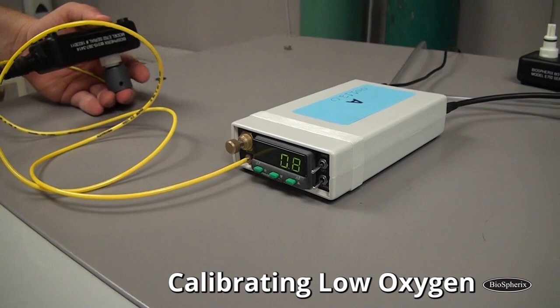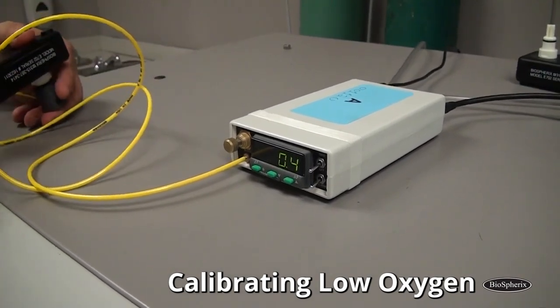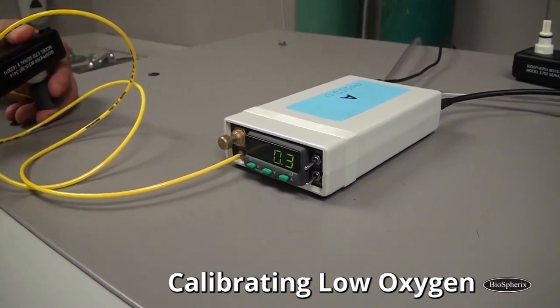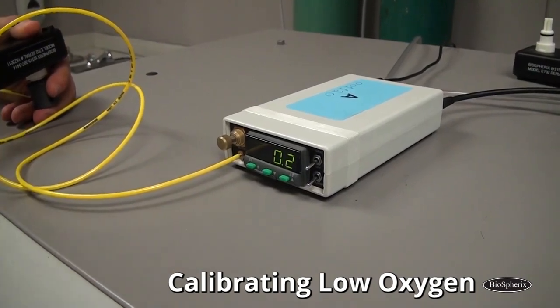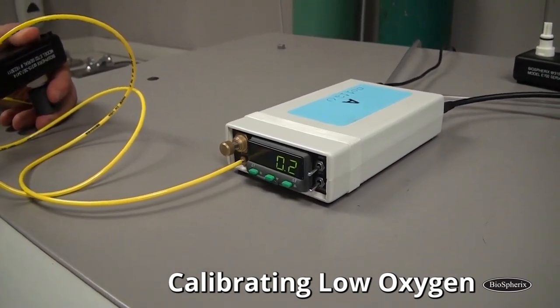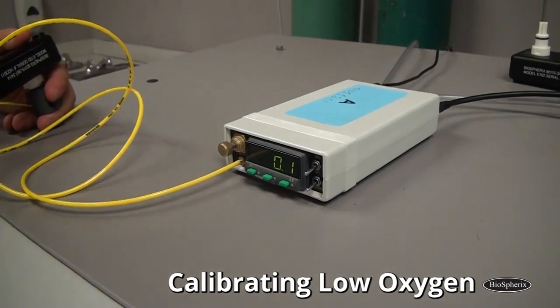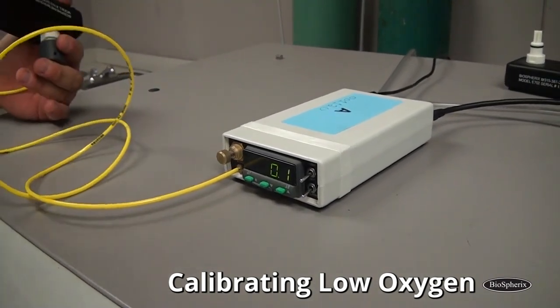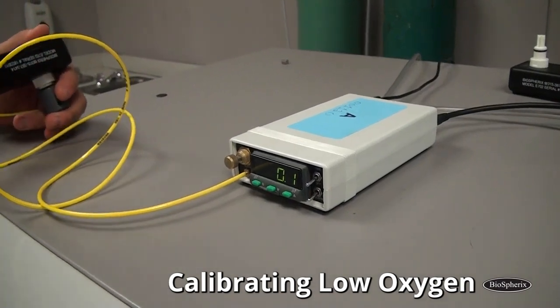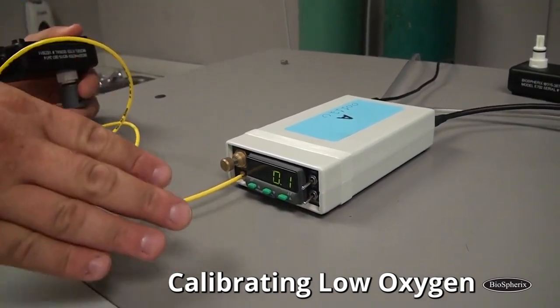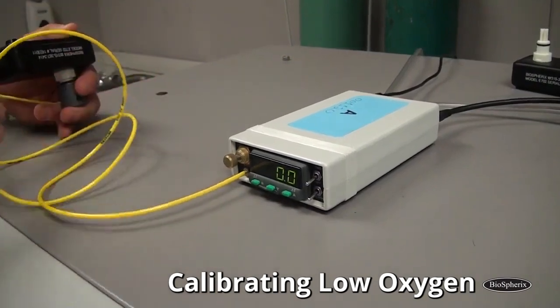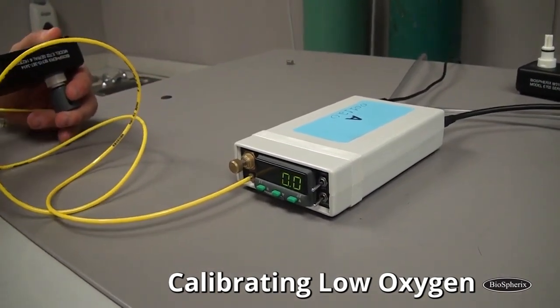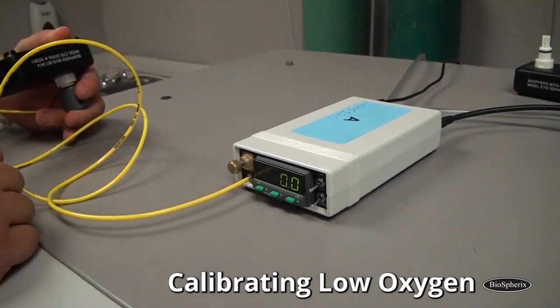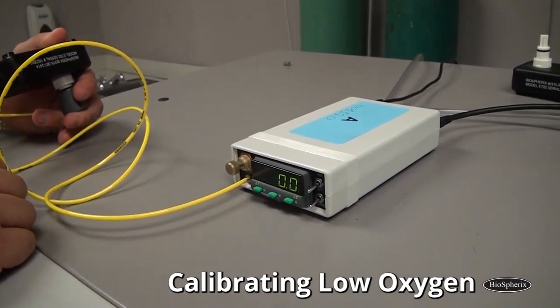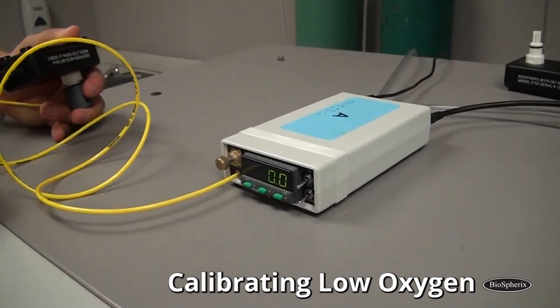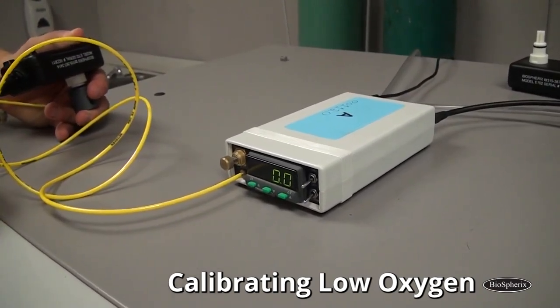A lot of times it will, other times it'll be off a little bit and we'll have to make a little adjustment. But we just let it run until it stabilizes here. It usually takes about 2-3 minutes. You don't want to let it just keep running. Sometimes people will ask us, should I let it run for 20 minutes or what? No, that's way too long. You can see it goes down quickly, stabilizes out. I let it run for about 2 minutes. If I don't see it change for about 60 seconds, I know we're at zero. And it looks like we're right at zero, so we don't have to make a change.